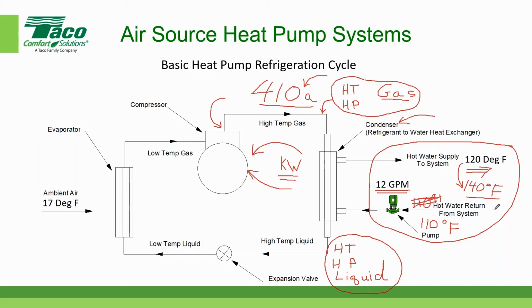Okay. So now that high temperature. Another question: what is getting the incoming water to 110 degrees? Well, you have a device. Ultimately, let's make it super simple, and let's say you have a fan coil out there. So I'm going to put a fan, and I'm going to put a coil, and I'm going to connect from the supply water piping here. So I'll go around my balloon there up to my coil. So I've got usually copper tubes, aluminum fins, that kind of stuff.